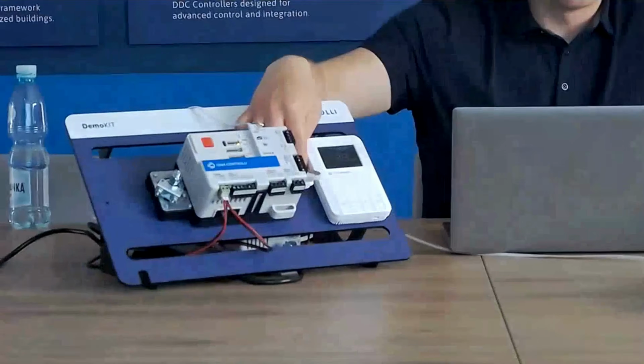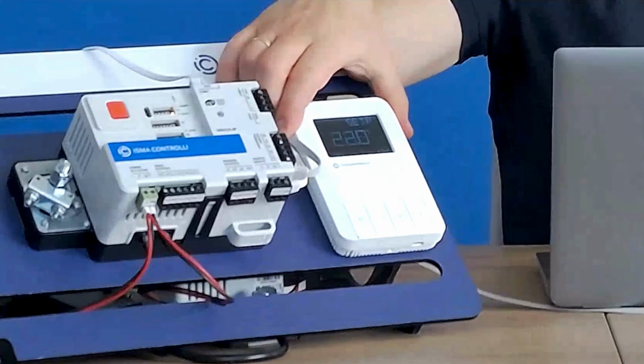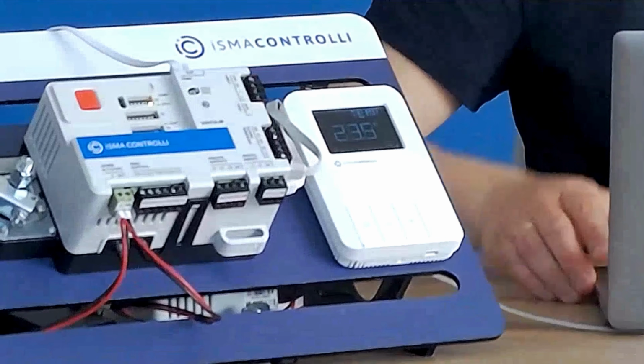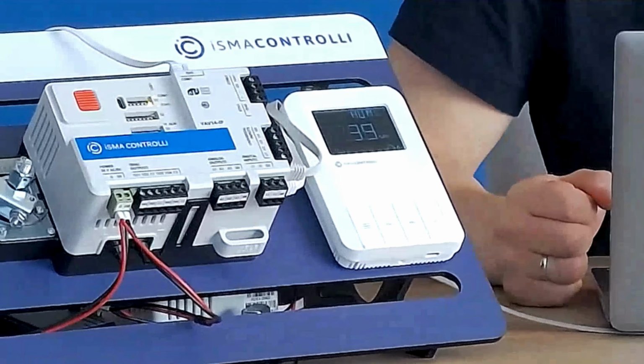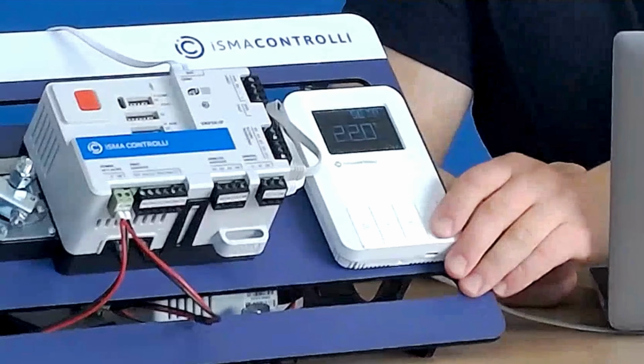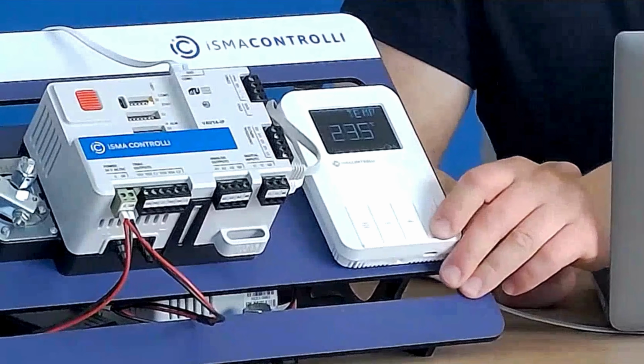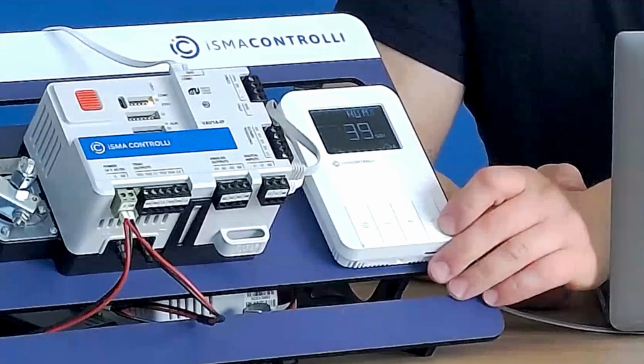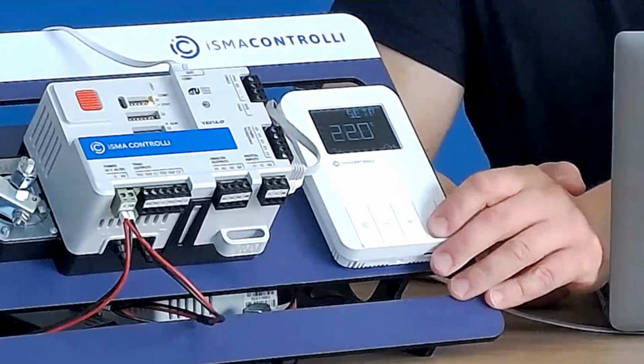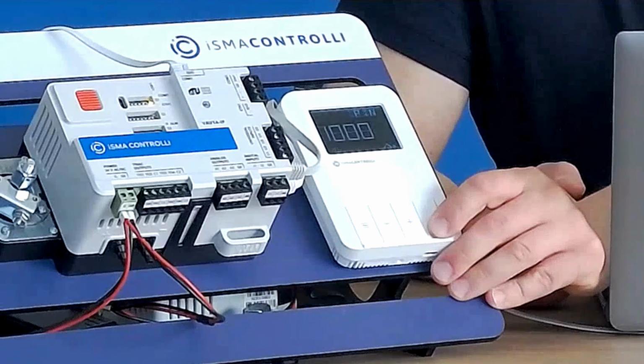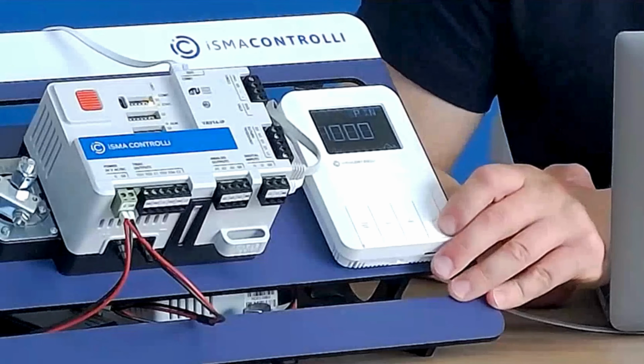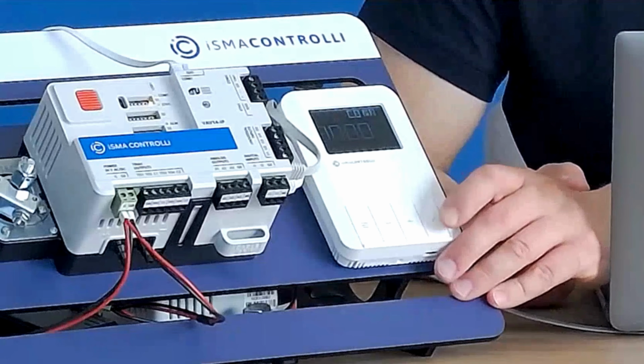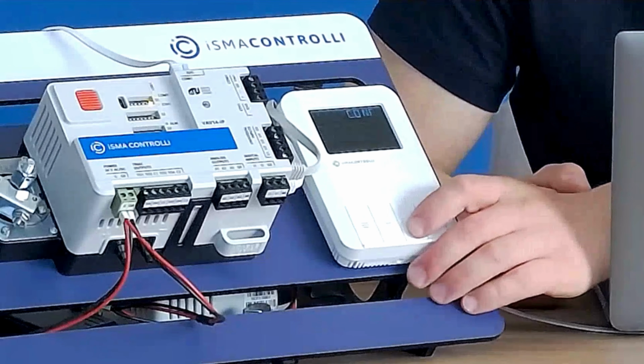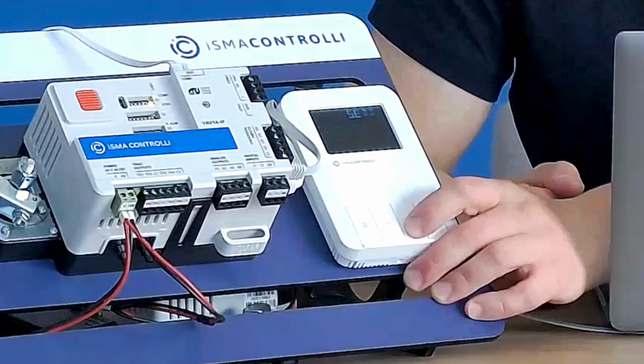So we have one set with the power up controllers, and we will start with the commissioning without any tool, without any computer. So I will just click the OK menu to enter the password protected submenu. I just need to hold for 3 seconds, and you can see that it's password protected. It requires a PIN. So 1000 is the default one. And I've got the configuration settings.